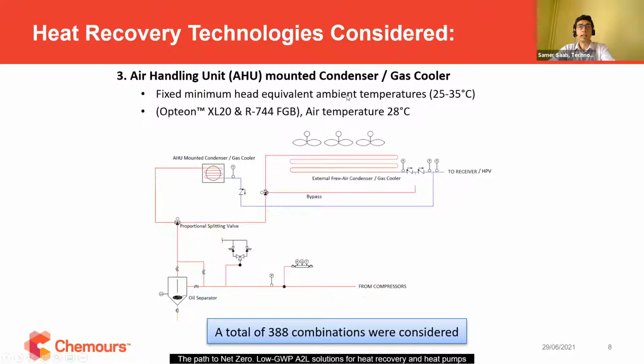This is what we commonly call to-water when talking about heat recovery with CO2. Finally, we have a direct air handling unit condenser or gas cooler, recovering energy from refrigerant directly to the blown air within the supermarket. In this case, we also have a set of valves that regulate or optimize the heat recovery while optimizing the condensing temperature or the gas cooler temperature.